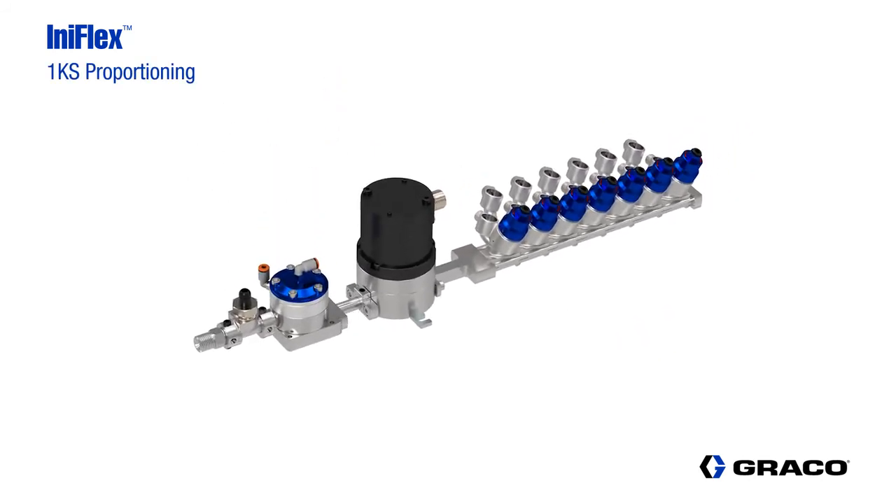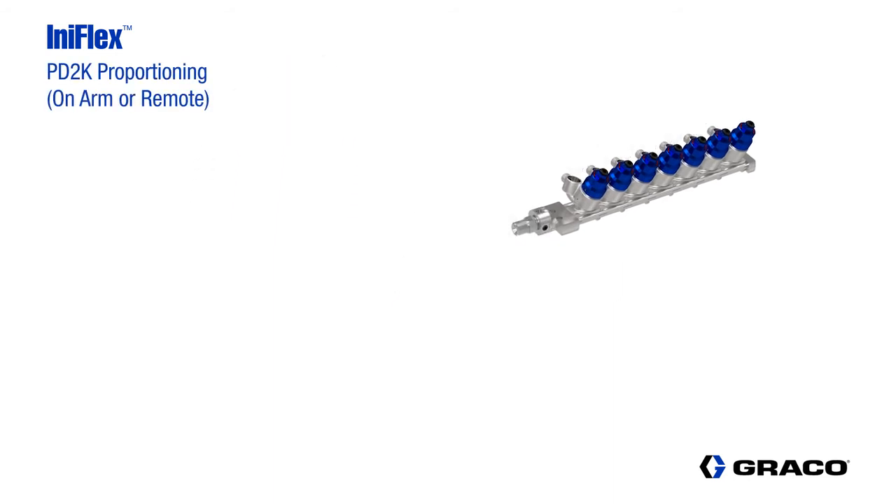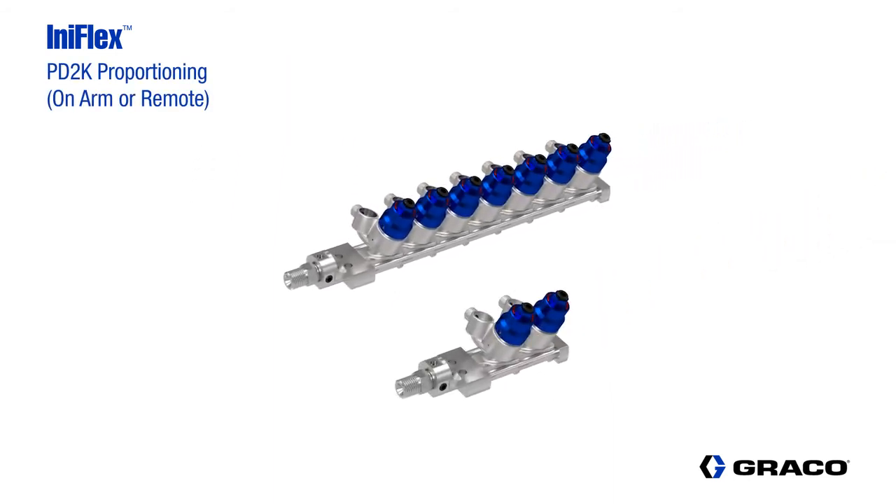For single component flow control with color change capability, we can use the color change stack, the fluid flow meter, and the fluid pressure regulator with the pressure transducer outlet connection. This simple setup can now be used with the 1KS flow control platform. Using the valve stack for the base component of a 2K material, and with the addition of a stack for the catalyst, the IniFlex solution can now be used with the PD2K platform for robot on-arm or remote mount applications.